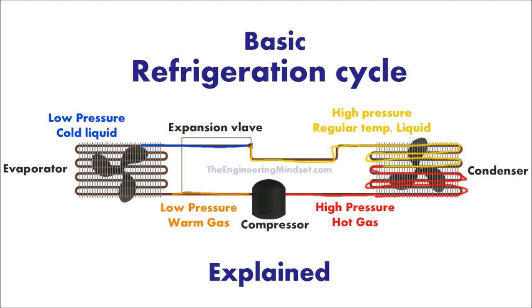So stage four, which is the last stage in the refrigeration cycle, and this happens in the evaporator. The refrigerant enters as a low pressure cold liquid and passes through the coil, which is a lot like the condenser. On the other side of the pipe is the air of the room which needs to be cooled. And the fan blows this warm air across the coils. This allows the air to be cooled by the cold refrigerant within the pipe. And it also allows the refrigerant to pick up that heat and carry it away towards the condenser that we dumped later in the cycle.